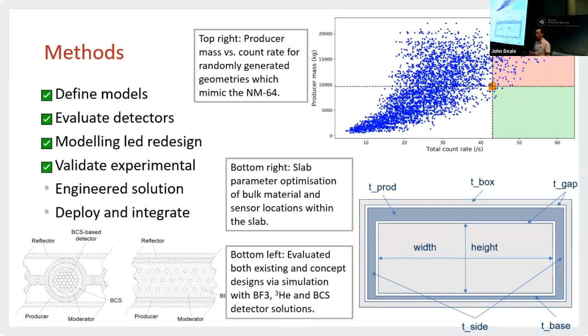We did an evaluation of detectors. We considered boron-coated straws as an alternative. We then did a modelling led redesign. Before we did that, we took a benchmark to see how good the NM64 was designed and how optimised it was for the mass of lead. Anything in the green box shows something that achieved a higher count rate for a lower mass of lead — very few beat the NM64, which is probably a result of oversimplification of our model. Anything in the red gets high counting efficiency but for a higher cost of lead, so it was very well designed. We then went to a parameterised model for the generation of thermal neutrons in the main detector location, optimised all of that, and came up with an optimised design for helium-3 detectors.